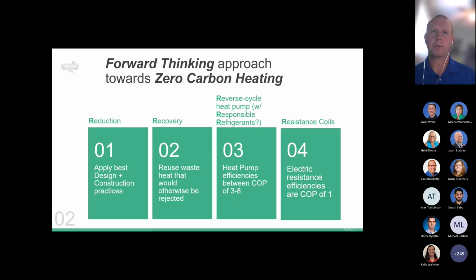Similar to that 4-step zero carbon approach, I put together this 4-step zero carbon heating approach. Step 1 is again reduce before you produce: why heat up to 75 degrees in the winter when we could maybe heat to 70 degrees? Those are simple reduction measures. From a recovery standpoint, a lot of things that didn't pencil out previously are starting to pencil out because we're putting a higher price on carbon.